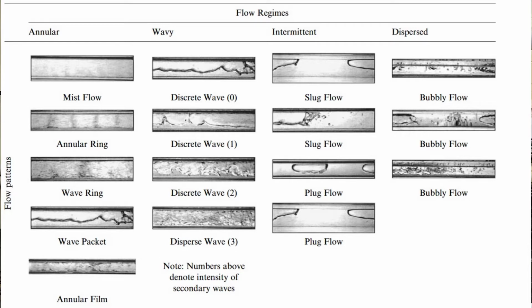So what you're looking at now is an image of several different videos taken at several different points in a typical condenser. Starting with the annular flow, you have a large quantity of vapor where barely any fluid has condensed, where you have very high vapor velocity and very thin liquid films. Moving on, you have sort of a wavy regime where you now have some condensate accumulating at the bottom of the tube. That's basically gravity doing the work, causing the pool to accumulate.